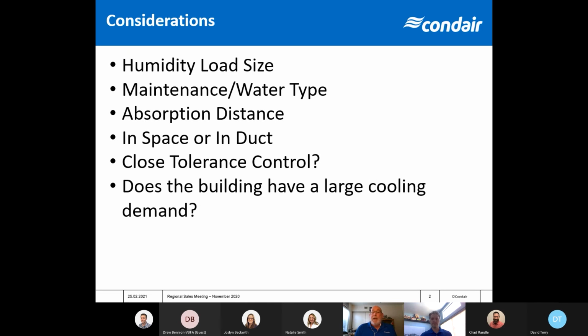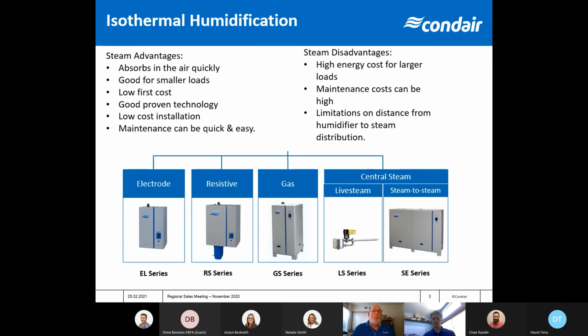And does the building have a large cooling demand? We can help with that as well. With our adiabatic systems, again, we're going to generate 1,000 BTUs of cooling for every pound per hour of humidity that we generate. So we can actually help provide some of the cooling for the building as well with those systems. We'll talk about that here in a little bit too. So the first products that we're going to talk about here are our steam humidifiers.